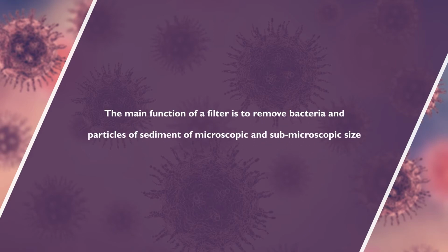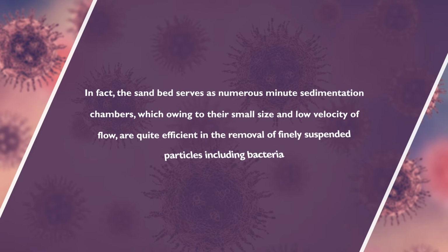Mechanism of filtration. The main function of a filter is to remove bacteria and particles of sediments of microscopic and submicroscopic size. In fact, the sand bed serves as numerous minute sedimentation chambers which, owing to their small size and low velocity of flow, are quite efficient in the removal of finely suspended particles including bacteria.